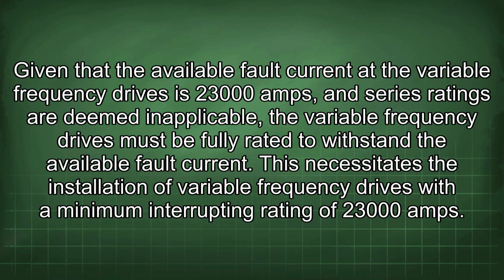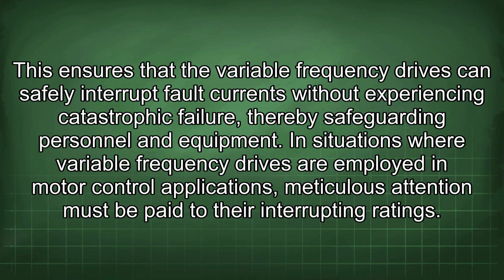Even if the available fault current at the variable frequency drives is 23,000 amps, and series ratings are deemed inapplicable, the variable frequency drives must be fully rated to withstand the available fault current. This necessitates the installation of variable frequency drives with a minimum interrupting rating of 23,000 amps. This ensures that the variable frequency drives can safely interrupt fault currents without experiencing catastrophic failure, thereby safeguarding personnel and equipment.